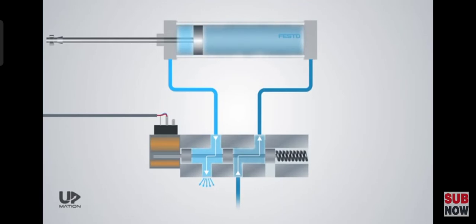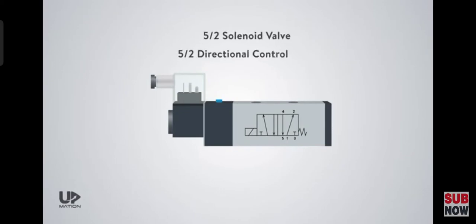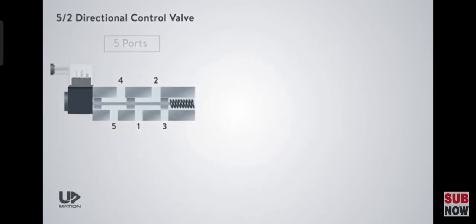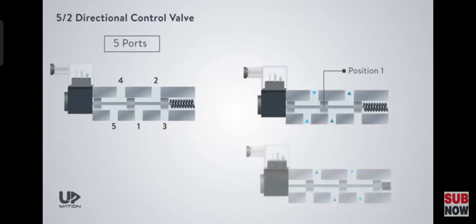Now, it's time to learn how these valves are called and how to read their graphic symbols. This valve is known as a 5x2 solenoid valve or a 5x2 pneumatic directional control valve. The first digit is for the number of ports the valve has. And the second digit is for the number of states the spool can be in.